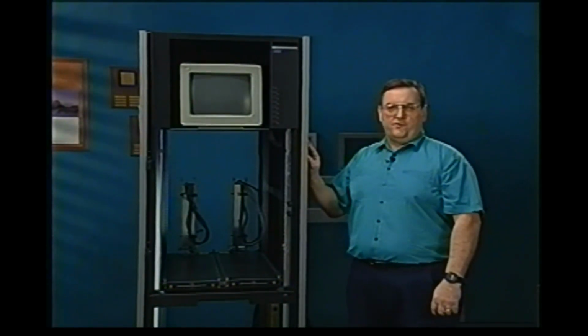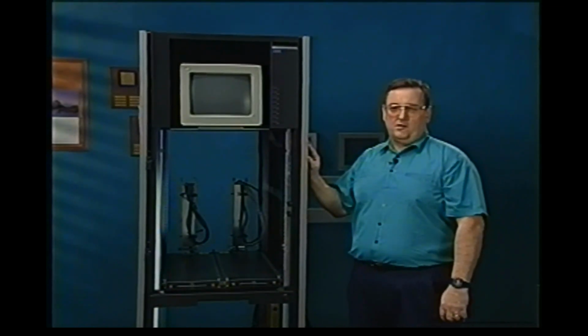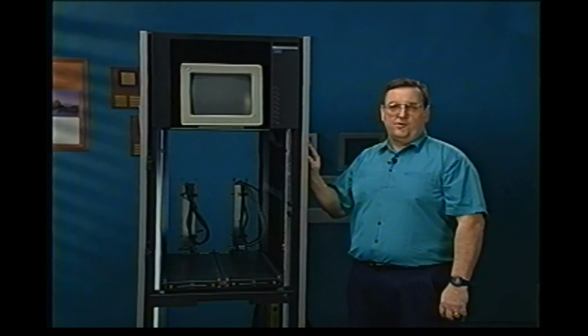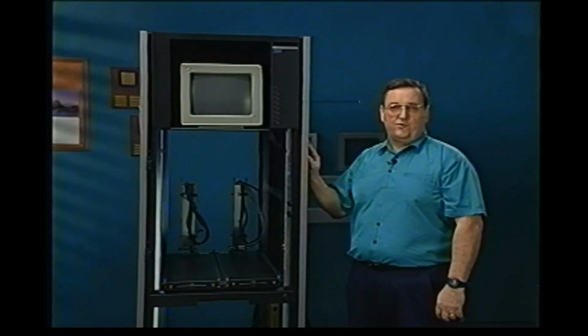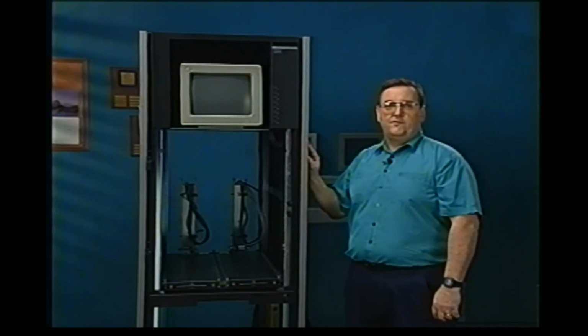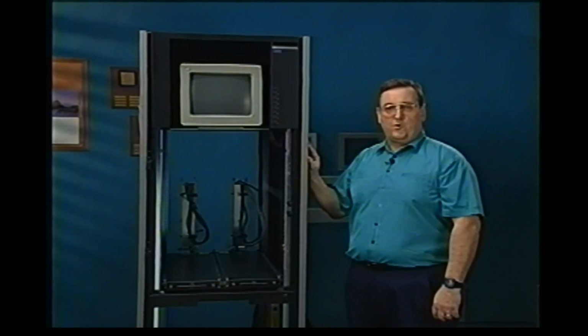Now let's install the servers, making sure you have the correct mounting tray assemblies for each server being installed. Always install servers in the bottom row first. This is to ensure cabinet stability. In this 19-inch model, a single drawer assembly is used to install a 520 or 720 server. Also, the servers installed may need a BIOS update to function properly. Check with IBM support to verify the BIOS levels required for the servers being installed.